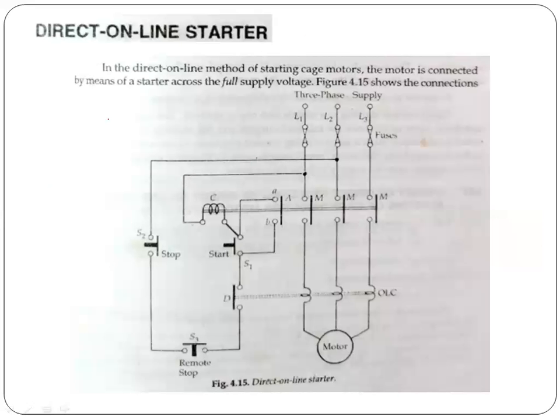Now we will start with the direct online starter or DOL starter. In the direct online method of starting cage motors, the motor is connected by means of a starter across the full supply voltage, as the connections are shown in this figure. Here we have different switches. This is the starting switch and these two are stopping switches, and this is the energizing coil, and this is the three-phase supply point, and these are the fuses, and these are the contacts, and this is the overload coil. So now we will discuss how the DOL starter is used for starting purposes.